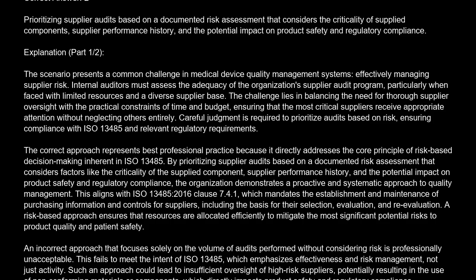Careful judgment is required to prioritize audits based on risk, ensuring compliance with ISO 13485 and relevant regulatory requirements. The correct approach represents best professional practice because it directly addresses the core principle of risk-based decision-making inherent in ISO 13485. By prioritizing supplier audits based on a documented risk assessment that considers factors like the criticality of the supplied component, supplier performance history, and the potential impact on product safety and regulatory compliance, the organization demonstrates a proactive and systematic approach to quality management. This aligns with ISO 13485, 2016 Clause 7.4.1, which mandates the establishment and maintenance of purchasing information and controls for suppliers, including the basis for their selection, evaluation, and re-evaluation. A risk-based approach ensures that resources are allocated efficiently to mitigate the most significant potential risks to product quality and patient safety.